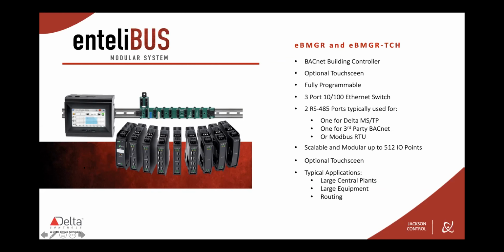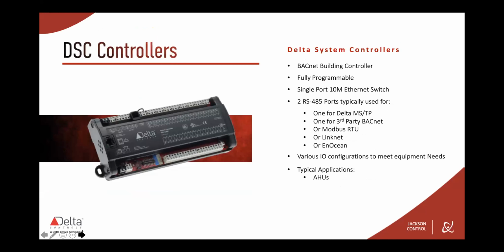Typical applications for these are large central plants and large equipment. The EB Manager itself can also be used as a router, say between a large BACnet MSTP network and a BACnet IP network, or for an older IP network using BBMD or something along those lines. So there are lots of different applications.